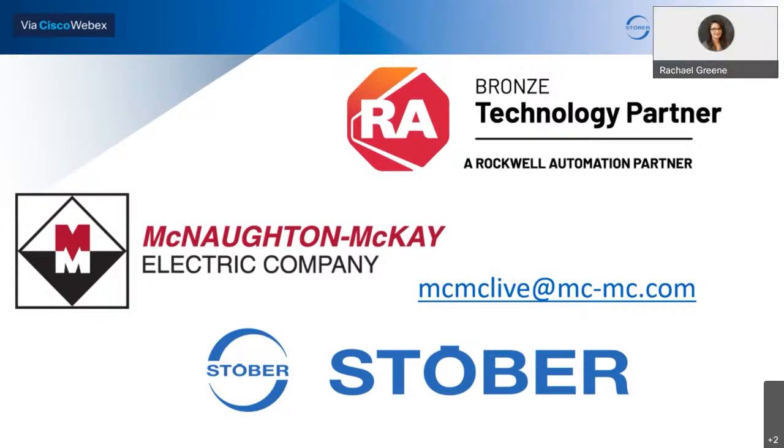Wonderful. That makes it a lot easier on our customers, and a lot of different options there. And with the servo stop safety brake, does the Rockwell Automation publication show me how to size this? No, there's a lot of factors that go into the servo stop, and we're looking at inertias of the loads, and we're looking at stored energy, and the 60-something page book by Rockwell really goes into the integration of this product into the GuardLogix and GuardMaster controller. It sets up the wiring diagrams, and it sets up the ways of programming that and integrating that into your system. So that is something that STOBER takes on when you want to use one of these. We work with the distributor and the end customer, get the data, go back and forth, and size it appropriately so that there's no question, because it is really a safety component. We want to make sure we're part of that.